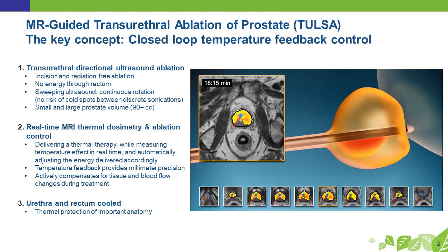It's a transurethral approach. It's a planar ultrasound transducer. There are 10 5-millimeter transducers in an array on the probe that's introduced into the prostatic urethra, each one individually controlled. The technology compensates for heat sinks, tissue temperature resistance, and blood flow, so that really what you see is what you get. If the tissue reaches the target temperature, the effect has been achieved. There's also cooling of the urethra and rectum to protect them.